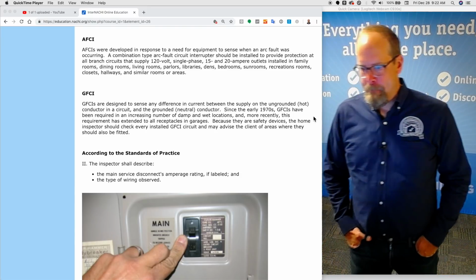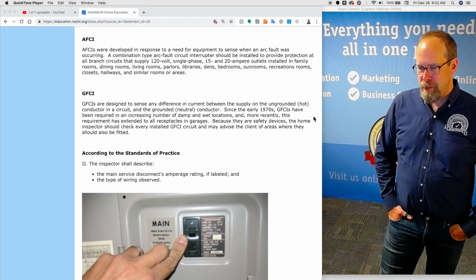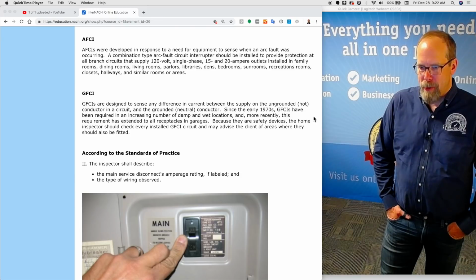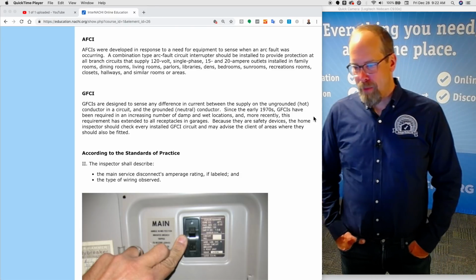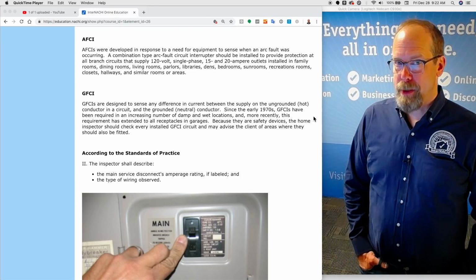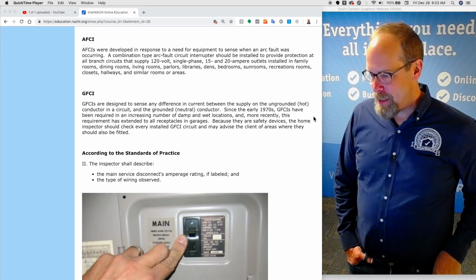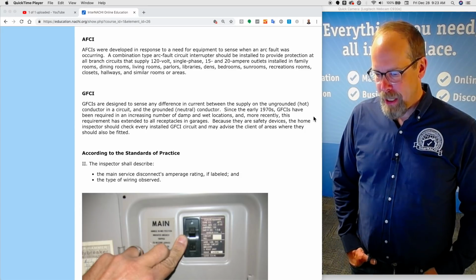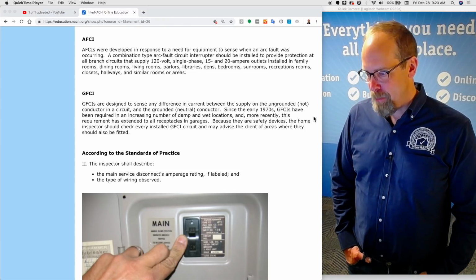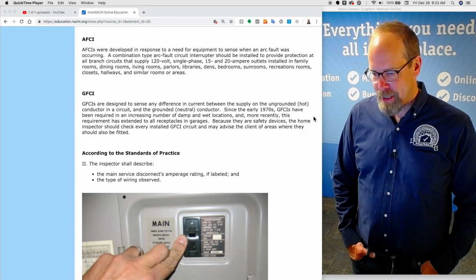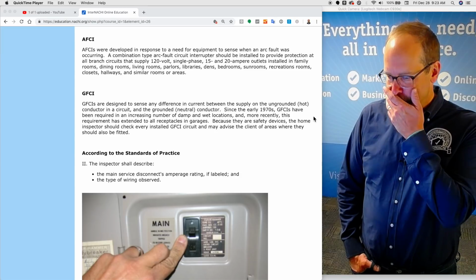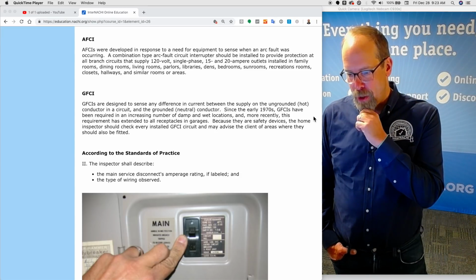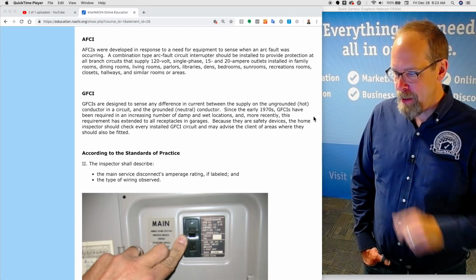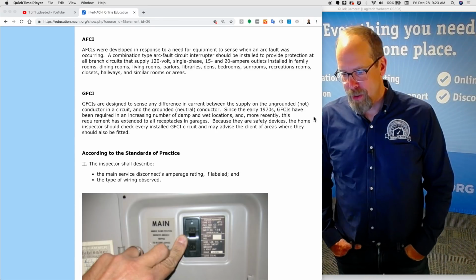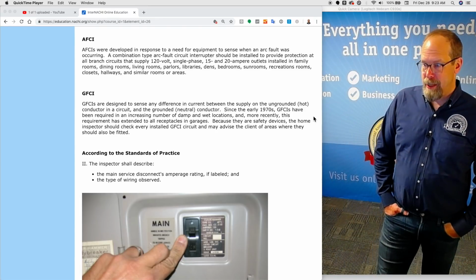GFCIs are designed to sense any difference in current between the supply of the ungrounded hot conductor, the black wire, in a circuit, and the grounded neutral conductor. Since the 1970s, GFCIs have been required in an increasing number of damp and wet locations, and more recently, this requirement has extended to all receptacles in the garage. Because they are safety devices, the home inspector should check every installed GFCI circuit and may advise the client of areas where they should also be fitted.